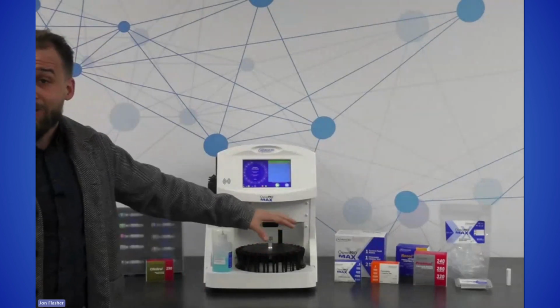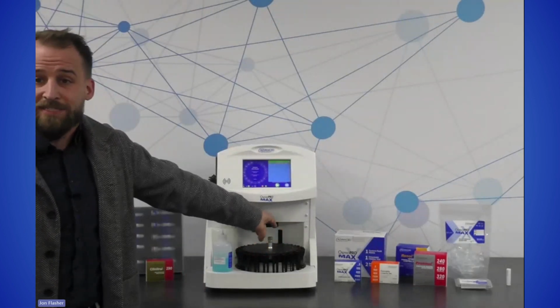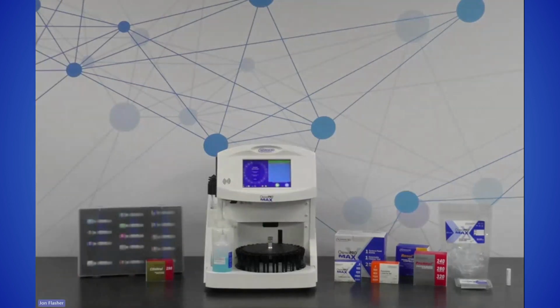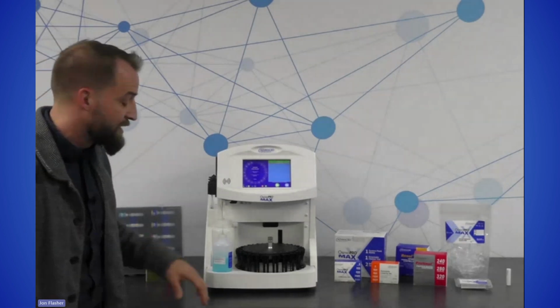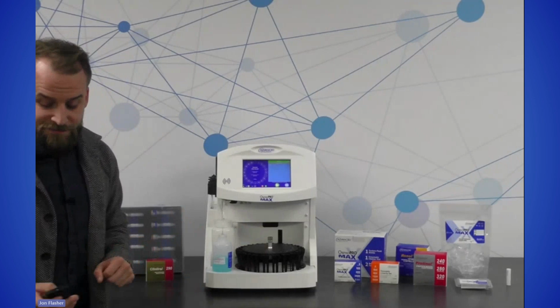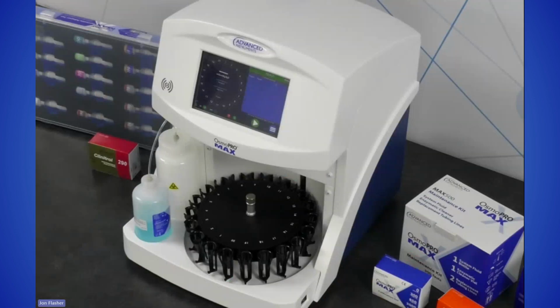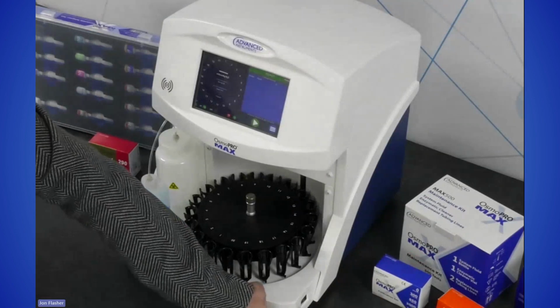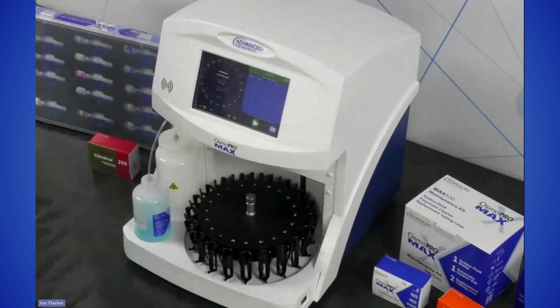Behind the carousel here, you'll see this little dark rectangle in the back. That's where the onboard scanner lives. That will actually scan the samples that are being run through the carousel, the 20-position carousel, which we have right there. On the side of the instrument, you'll see this little USB port. That is handy for exporting data from the instrument, so results or QC results, or a Levey-Jennings plot. I'll show you how to make one of those in the software later. So that's handy as well.